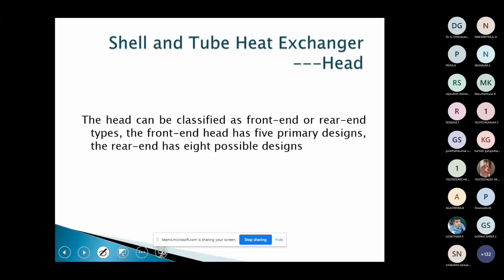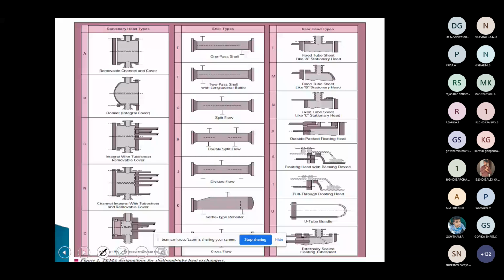Right. First, we will see the head. The head may be a front end or rear end type. For front end we have 5 designs, and for rear end we have 8 designs. You can see the types of heads. So these are the 5 front heads available. Depending upon the process and our requirement, we can choose any one of these heads for the heat exchanger. Coming to the shell types, we have these kinds of types. This is for 1 pass shell side, 2 pass shell side, split flow, double split flow, divided flow, kettle flow. These things we will see one by one, right? And these are all rear head types.